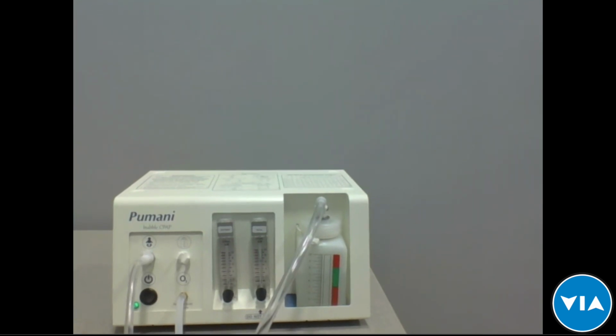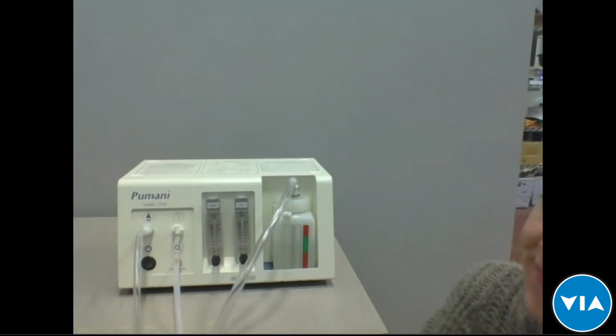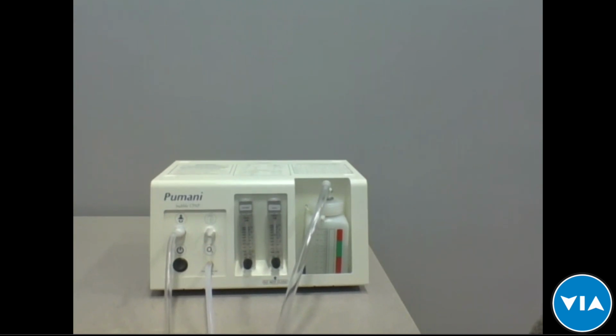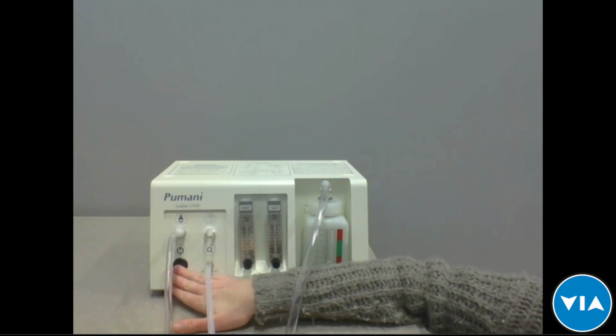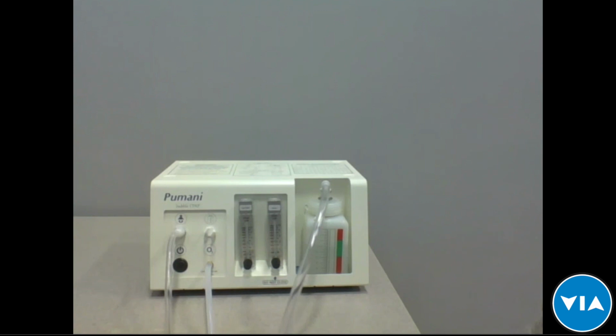And then you would connect to the baby, and it would continue to bubble. Periodically, you'd need to check that it was still bubbling, and that the flow meters were still saying what you wanted them to according to your recommended guidelines. Then you would know that it would continue to work. Of course, with anything, water evaporates, electricity goes out, the concentrator might be used by somebody else, the baby might move a bit, the prongs might come out. So it's continuous monitoring and doing all those basic checks on a regular basis that is key to giving effective treatment and having the machine work. So that's the basic demo, and I'm open for more questions, to go into detail about any of that or further explain.